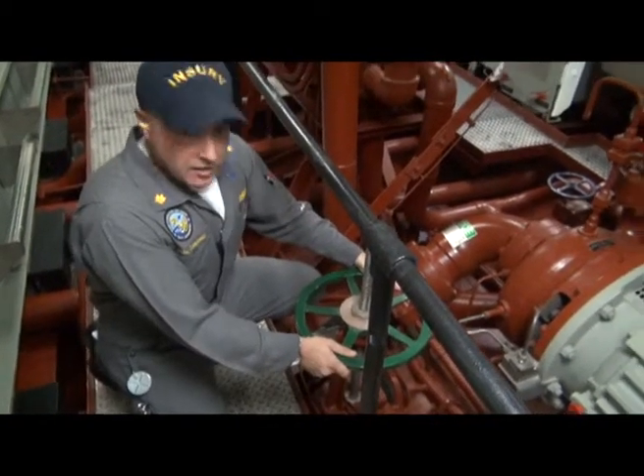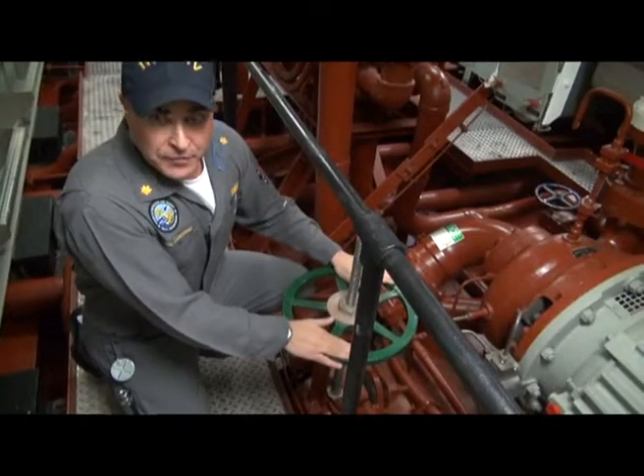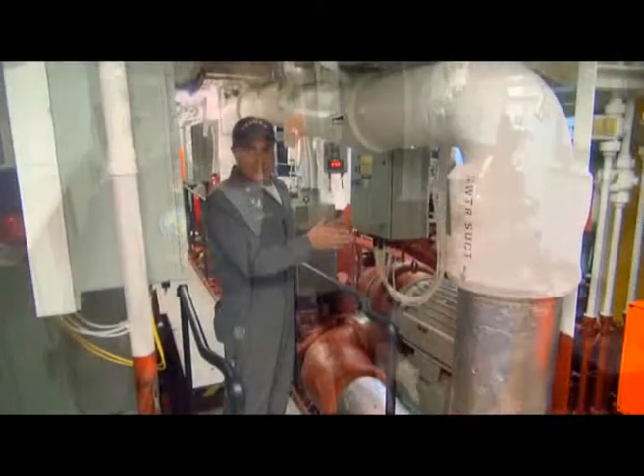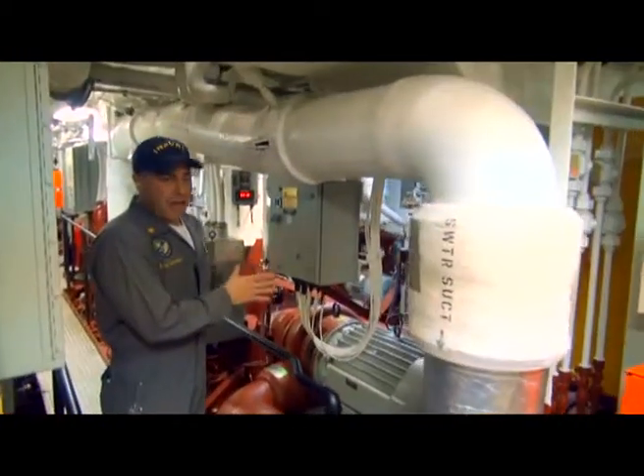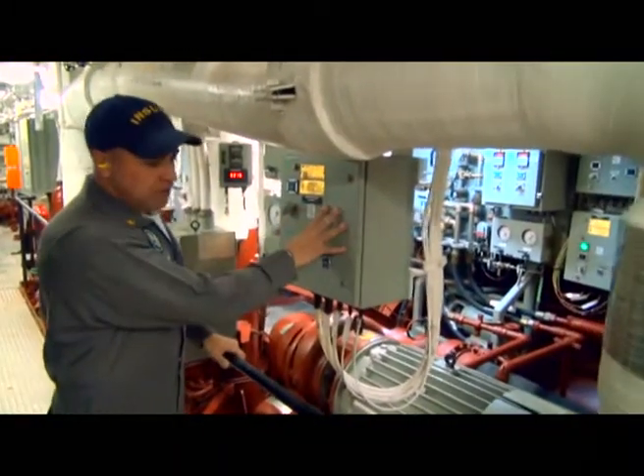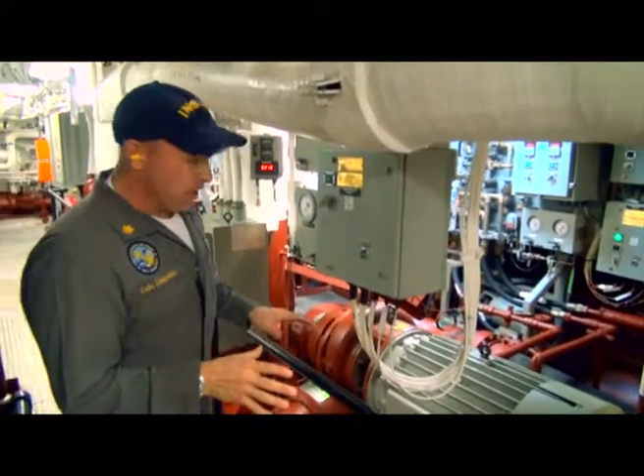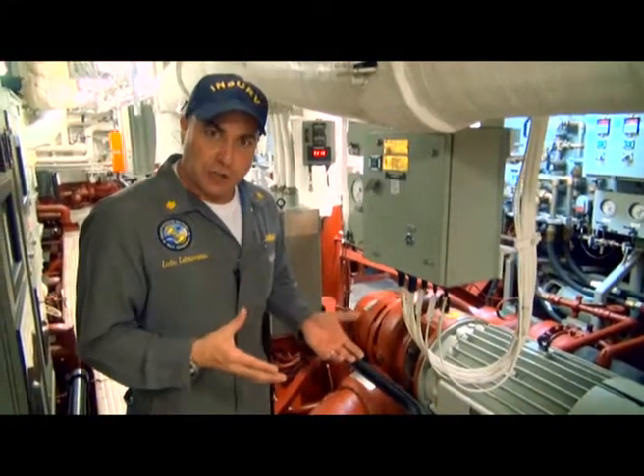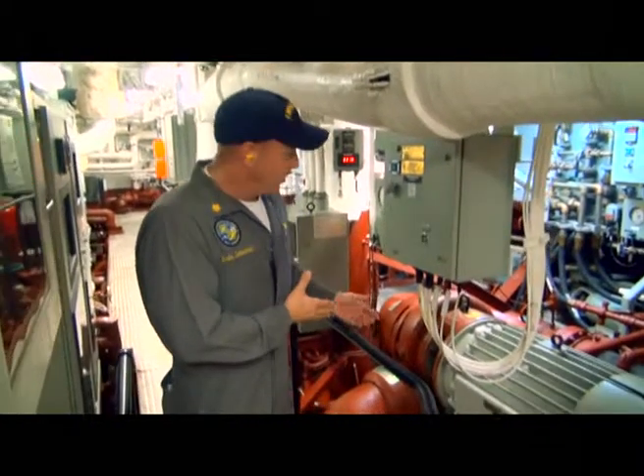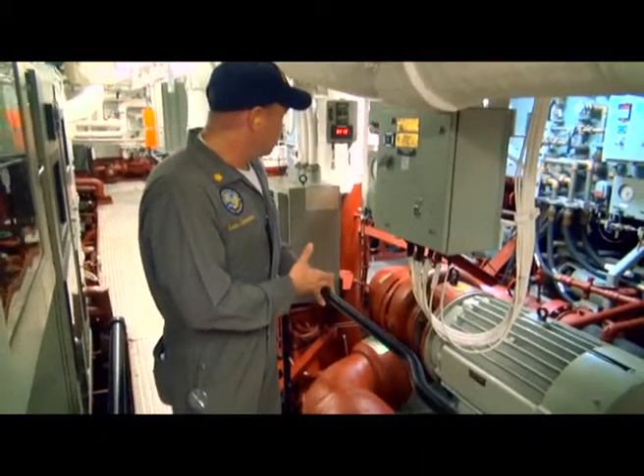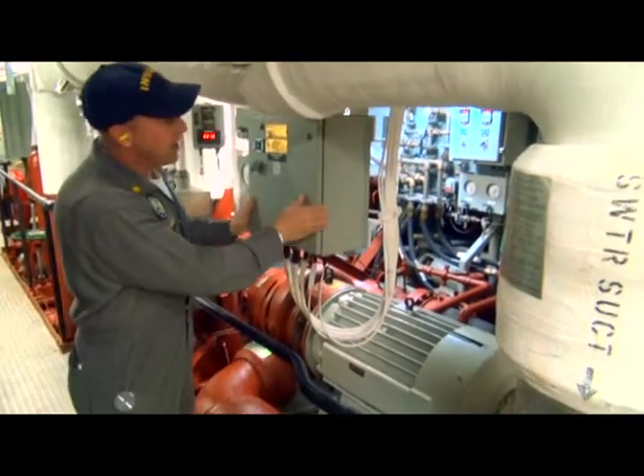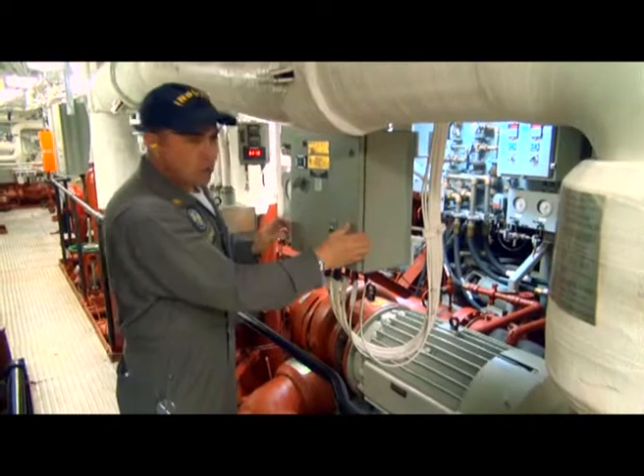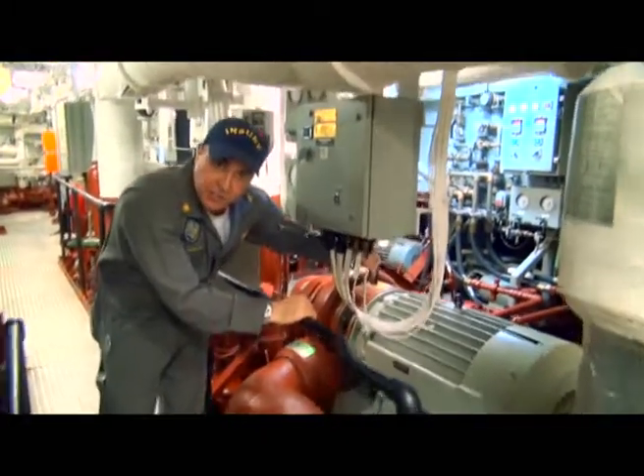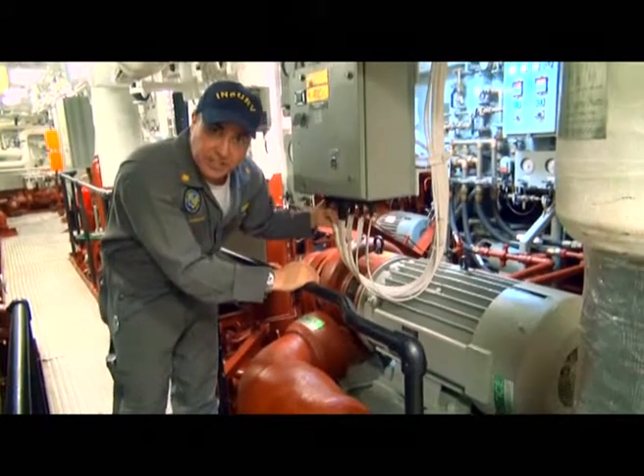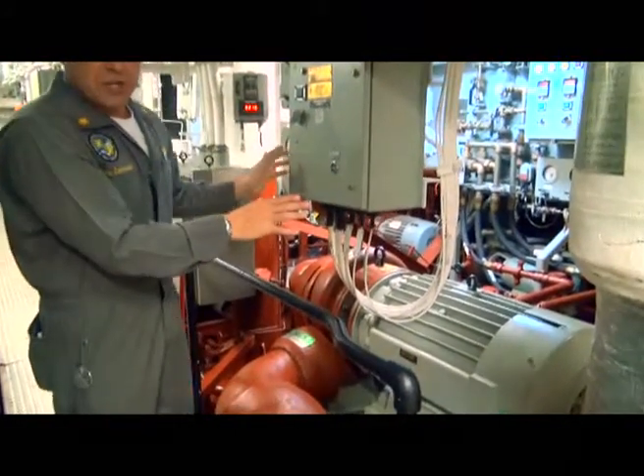Once the interlock is checked, the operator will open this valve, then we're ready to start the pump. First thing we want to do is start the pump locally. So we'll have the operator place the pump in local and start the pump. Once the pump starts, we check all the basic things we normally check for operation of the pump. We check the suction pressure, the discharge pressure, proper rotation, and we check for leaks. Even before we start, we check this motor controller, make sure it's intact, make sure these wires have no open stuffing tubes, and there are no safety hits on this motor controller. We check all that before we typically start.